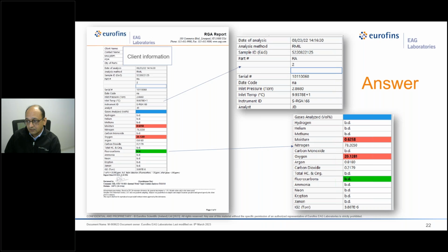And we also have at the bottom a conversion from volume percentage to ppm. So 1 volume percent is 10,000 ppm. That conversion is sometimes useful because when I say 5,000 ppm of moisture, that is basically 0.5 volume percent. Now in this particular case, we are talking about 6,258 ppm of moisture. We also get some questions: what is the volume percentage versus ppm? Is it a standard, or how to look at it?